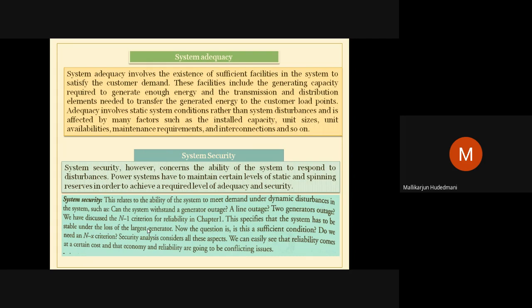Is it in danger? Is it secured? Able to cope up with the changes it is experiencing right now? If it is able to cope up, your system passes N-1 criteria acceptance. Likewise, it can be N-2, N-3, up to N-x. That makes the system secure. Even if two components go out, the system will be intact. If six components go out of control, the system is intact. This kind of security assessment analysis needs to be performed in the computer, in the energy center.